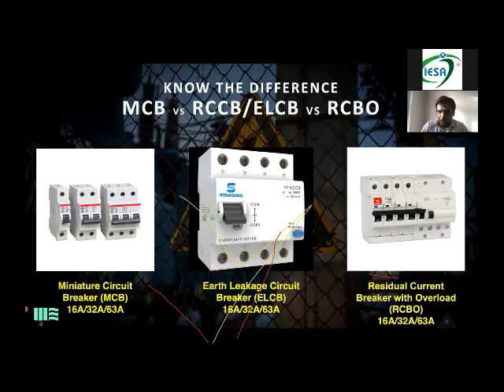Okay, and there's one last question from Ravinder. Although you have already answered this, he wants to know: during shows, if you face the problem of a power cut, even with a genset on, what precautions can we take so that it doesn't happen in future? Although you all have those backups and synchronization, probably he was not there at that time. Yeah, so again, it all depends. If the power goes, you need to have a backup. When I am doing a high profile kind of event, I make sure I get synchronized gensets on site. I don't trust the normal generators, but if I have to, then we have automatic changeovers available, so that at least we know the power will come within 1 second.